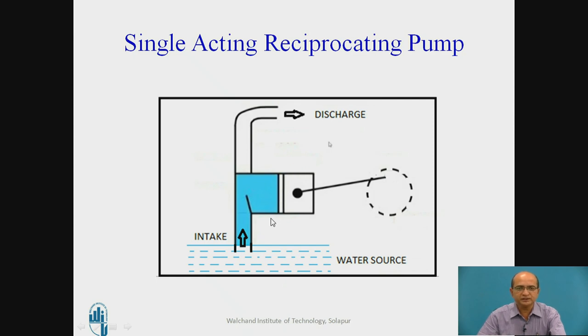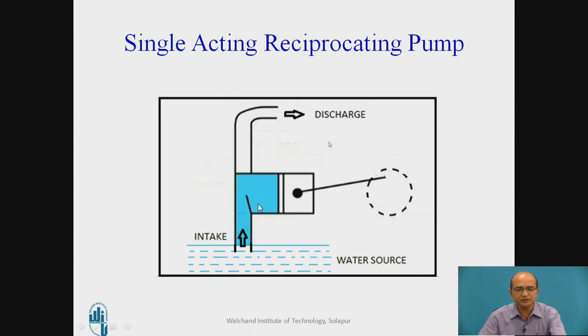One disadvantage is that there is an intermittent supply because water is sucked inside the cylinder only during the stroke from the inner dead center to the outer dead center. During that stroke, there is no delivery to the delivery pipe. So for half a rotation there is suction, and for the remaining half rotation there is discharge. This results in an intermittent supply, and the discharge rate is lower compared to the double acting reciprocating pump.